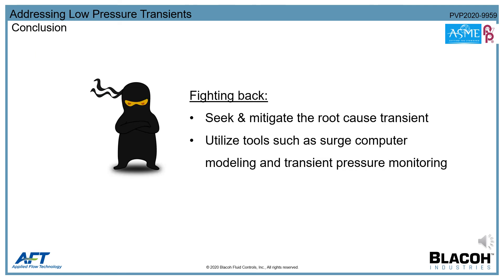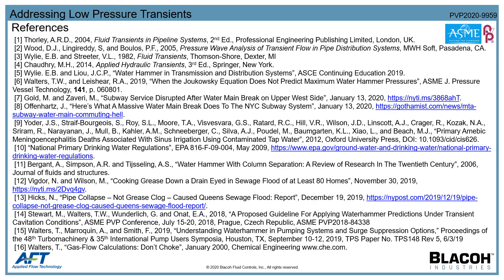Low pressure transient events, when unmitigated, can lead to a multitude of problems: abrupt and extreme pressure fluctuations that fatigue an already aged system, exposure of sensitive systems to contaminants through negative pressures, and unpredictable high pressures generated by collapsing vapor pockets. With the right tools and practices — such as transient monitoring and modeling — appropriate and effective solutions can be incorporated into piping system design, adding years of design life, reducing safety risk, and significantly reducing costs. Thank you for your time today.